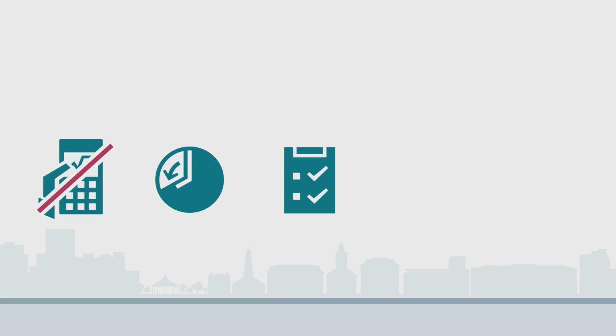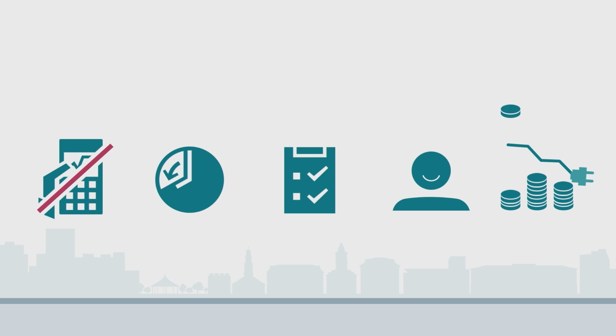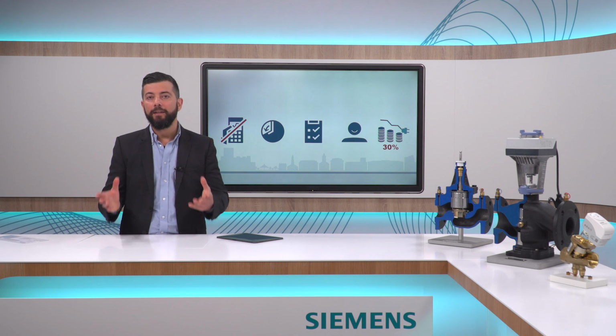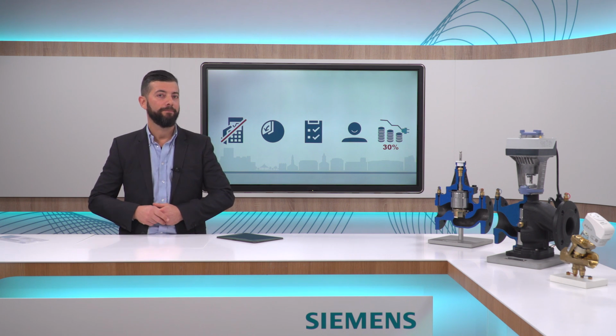On-site commissioning is extremely simple thanks to the easy max flow presetting and automatic balancing. And this is possible because dynamic valves ensure balanced water flow rates under all load conditions, thereby eliminating any impact of fluctuations in the room temperature. This way, dynamic valves allow for energy savings of up to 30% with no sacrifice of comfort. In other words, dynamic balancing is the right way of doing balancing.